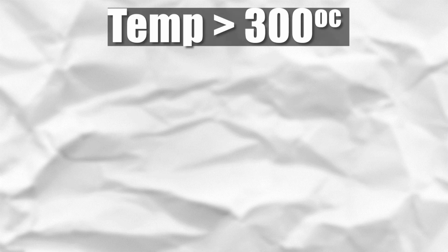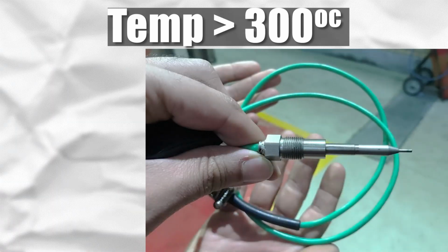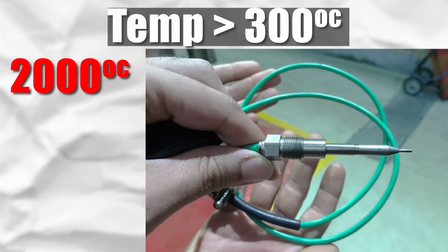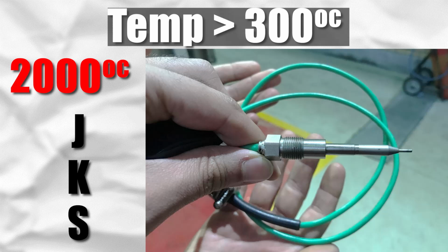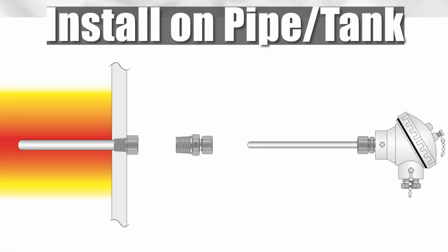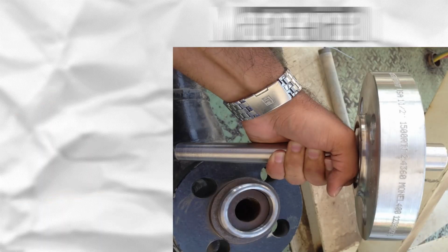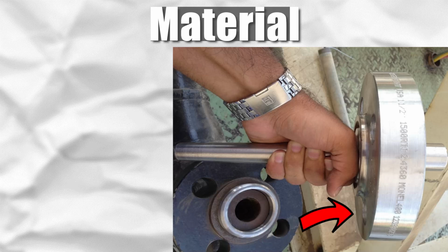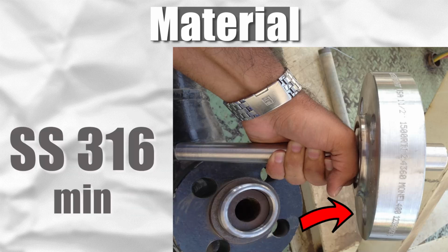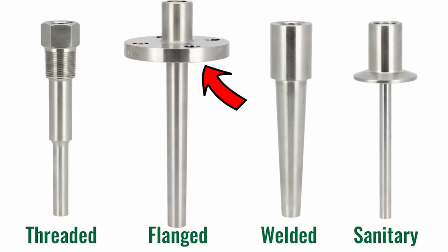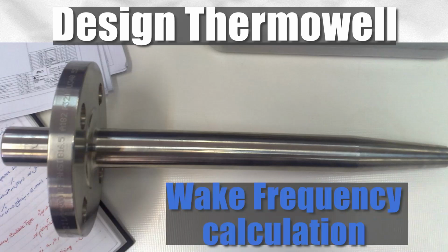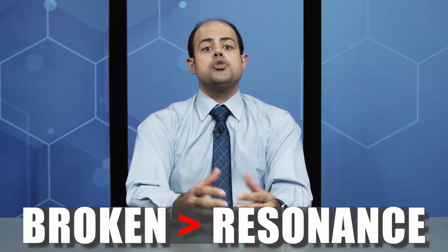For temperatures greater than 300 degrees centigrade, it is highly recommended to use thermocouples, which are designed to measure around 2000 degrees centigrade. Types J and K and even S are the most famous types in industries. To install a temperature measuring device on a pipe or a tank, we must use a thermowell. It is a kind of sheath to protect the instrument. As you may expect, the construction material of a thermowell is stainless steel 316 as a minimum. The type of connection can be fulfilled via flange or thread. To design a thermowell, wake frequency calculation is so important because the created frequency of vortices must not exceed 80% of natural frequency. Otherwise, the thermowell is broken due to resonance.